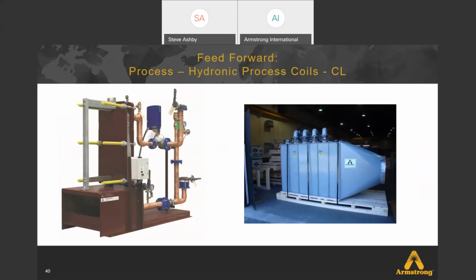So again, the way the internals of the valve position those two ports, in that scenario the hot port would be almost closed and that water just continues to go right back through to the coils. And all we would do is open that hot water port just a sliver to let enough hot water back in to maintain that set temperature. So it's what can be quite difficult for other heat exchanger packages, it's very easy for us with the Emech valve.